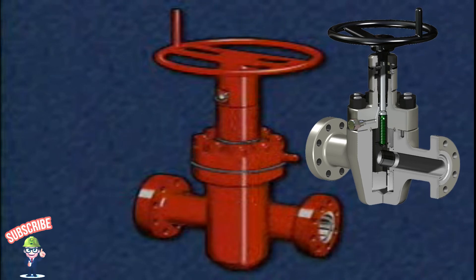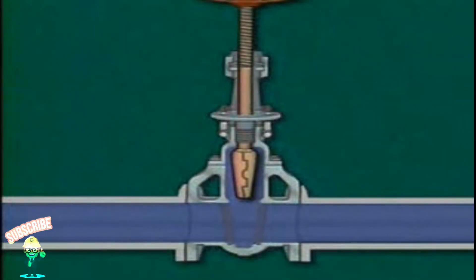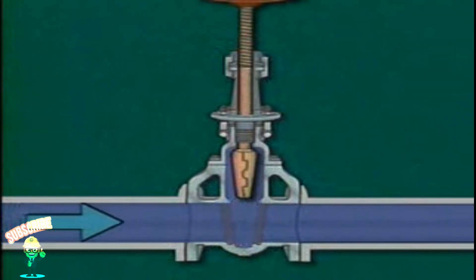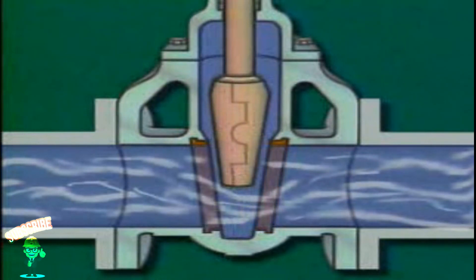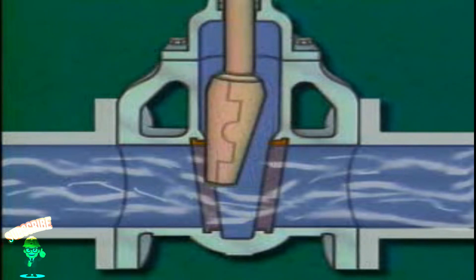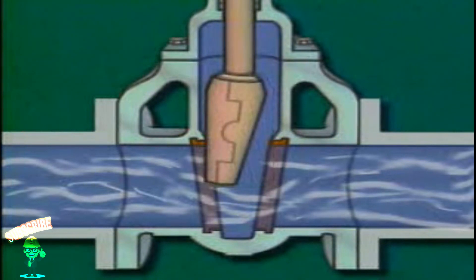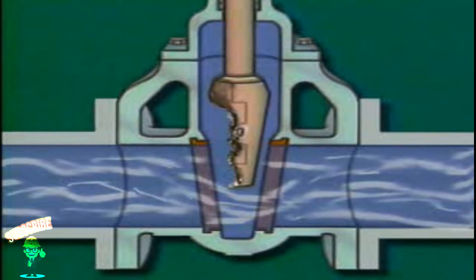Because no allowances for stem movement are necessary, a non-rising stem is useful in applications where space is limited. Gate valves work best when they operate in either the fully open or the fully closed position. When a gate valve's disc is completely raised, fluid flows straight through the valve with little obstruction. However, if the disc is partially raised, a space opens on either side of the disc and fluid passes under it, creating turbulence and causing the disc to swing from side to side, banging or chattering against the seating area. The chattering quickly leads to wear on the seat and the disc, and eventually the damaged valve won't be able to shut off flow even when fully closed. Also, the flow of fluid through a partially open gate valve wears the disc unevenly; in time, the edges most exposed to flow become eroded and the disc can no longer seat properly.